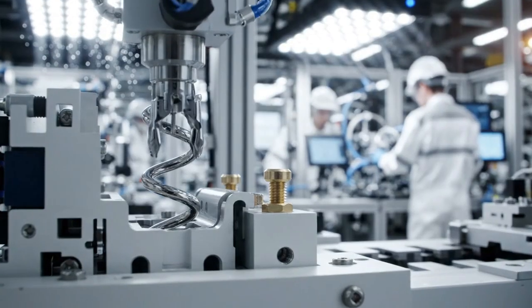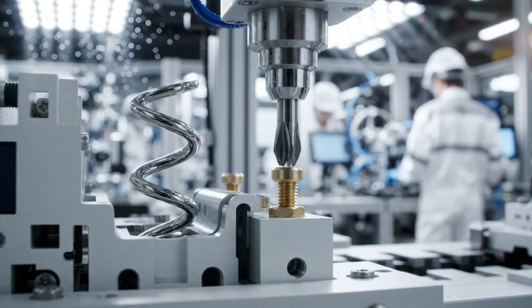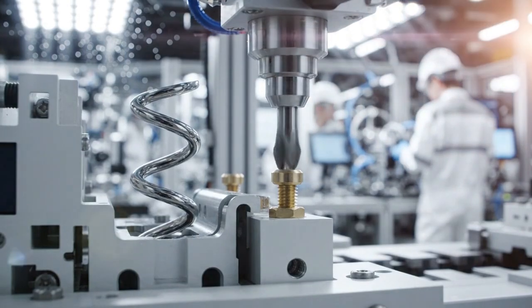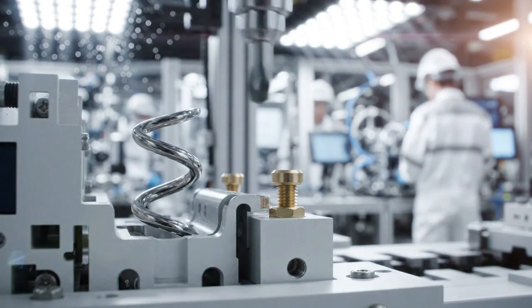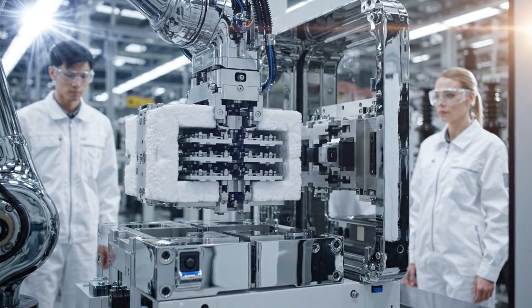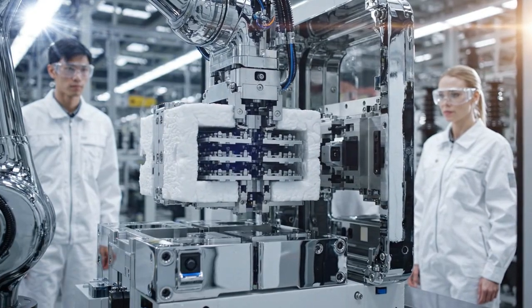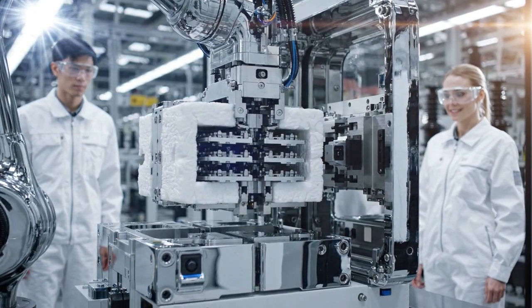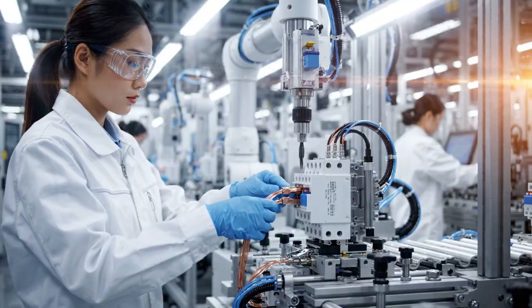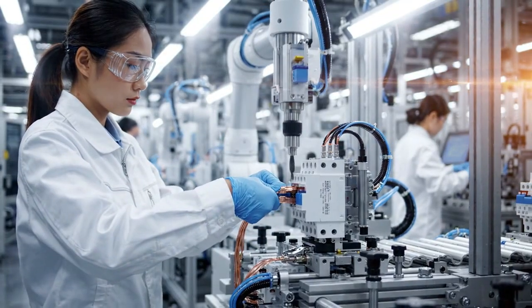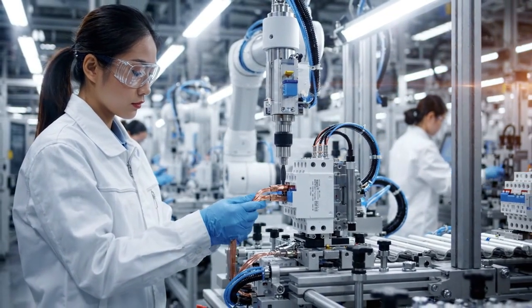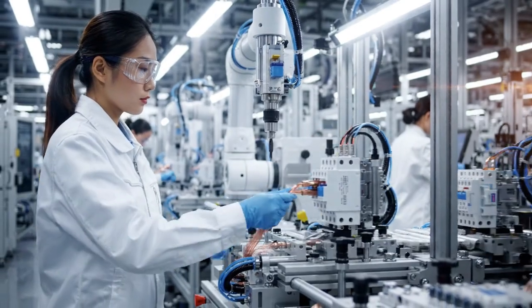Thermal calibration is the most critical assembly step. The calibration screw adjusts the bimetallic element trip point to match the exact rated current specification. The arc chute must be properly positioned to capture the fault arc immediately as the contacts separate. Misaligned plates would allow the arc to sustain itself. Terminal quality determines the reliability of the field connections. Every terminal must provide secure, low-resistance clamping of the customer's wire conductors.